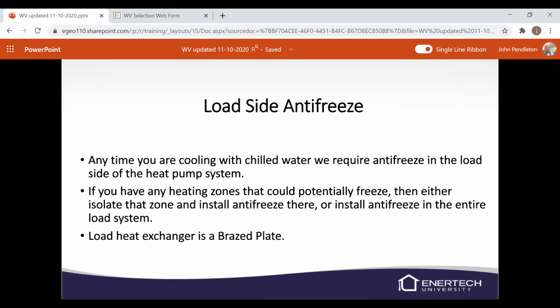Load side antifreeze. Anytime you're cooling with chilled water, we require antifreeze in the load side of the heat pump. Now, if you only have one zone out of 6 zones that are doing chilled water, you could install another heat exchanger in between those and isolate it, and then only put antifreeze in that one zone. That's totally up to you. But anytime we're doing chilled water, we want to make sure that it doesn't freeze and break something.